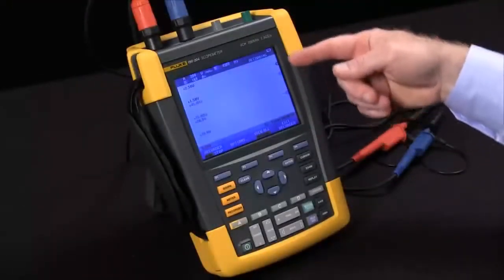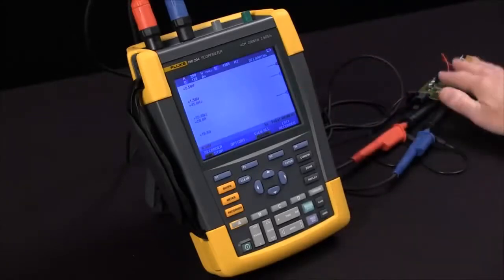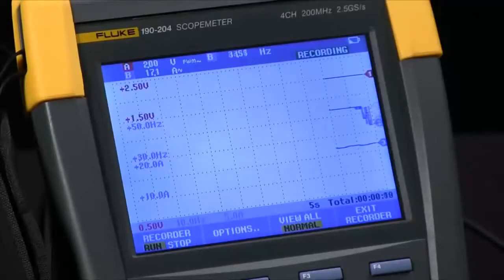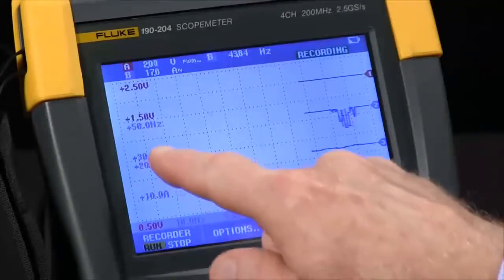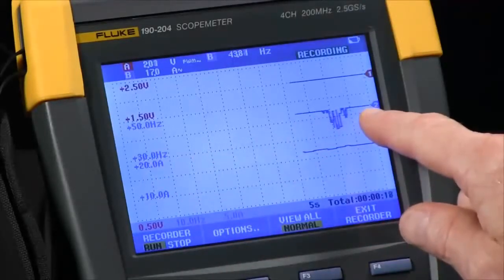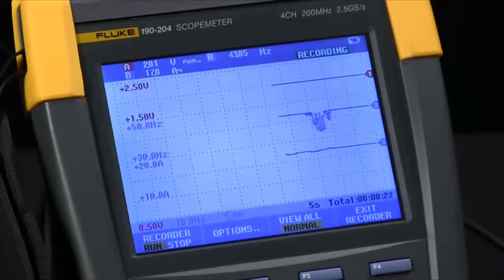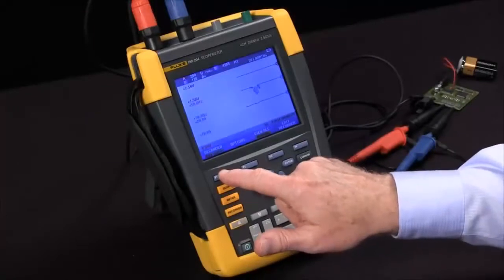And you start to see your readings coming across the screen. All 3 are there right now. We can actually record for up to 22 days with resolution down to 2 minutes. You can see your amperage is the bottom trace, your frequency on channel B is the middle one, and your voltage being the top. When you're ready to stop, you hit F1 to stop the recording.